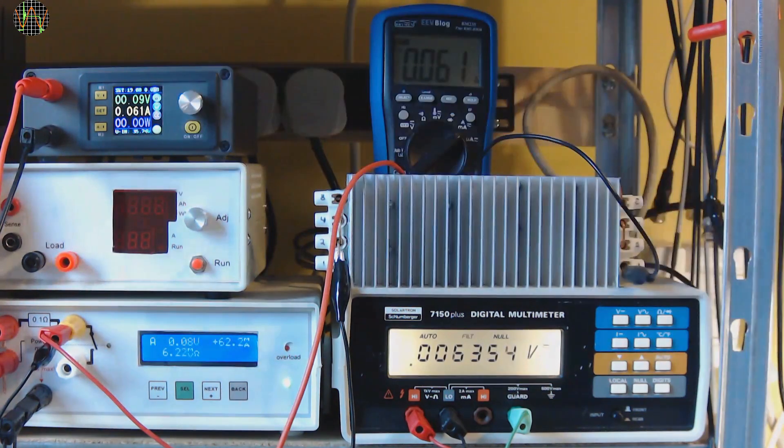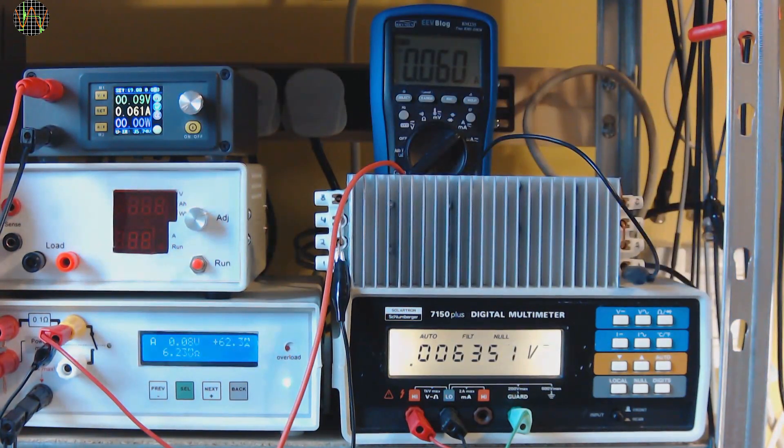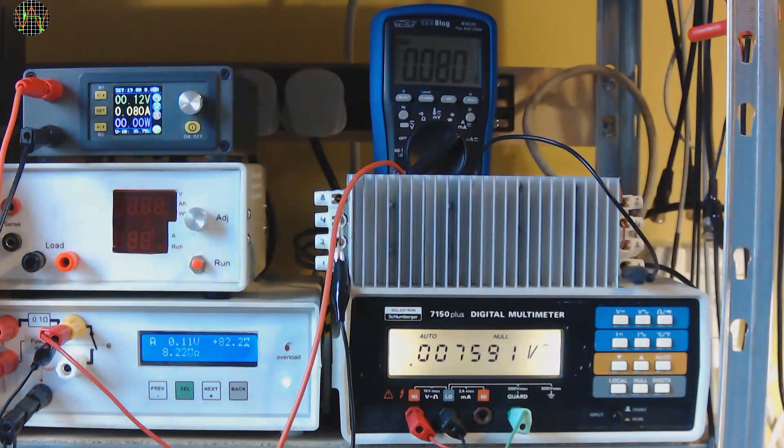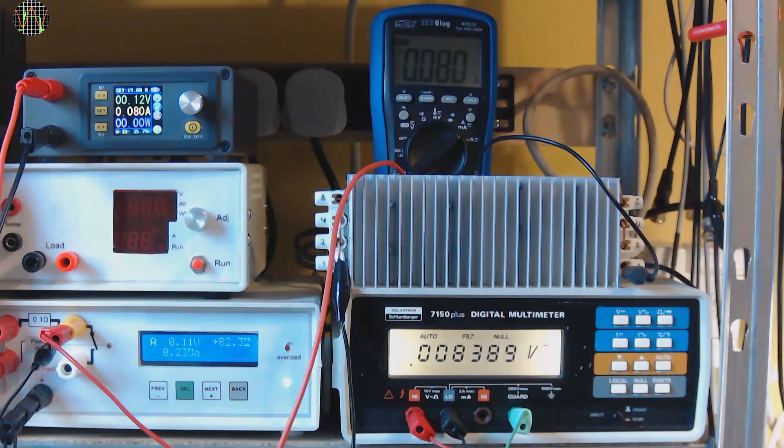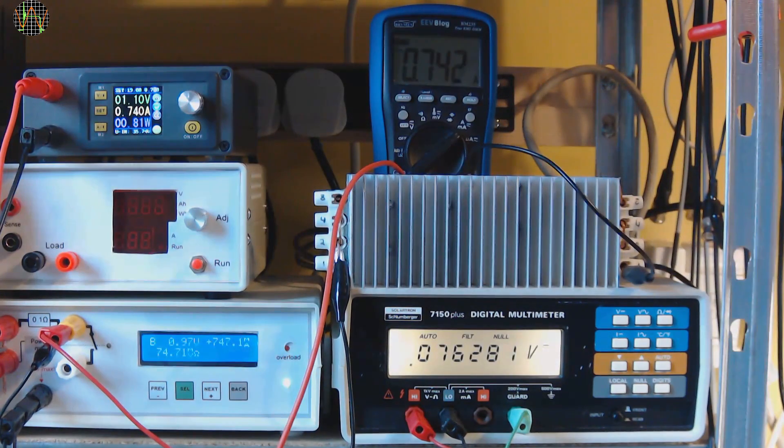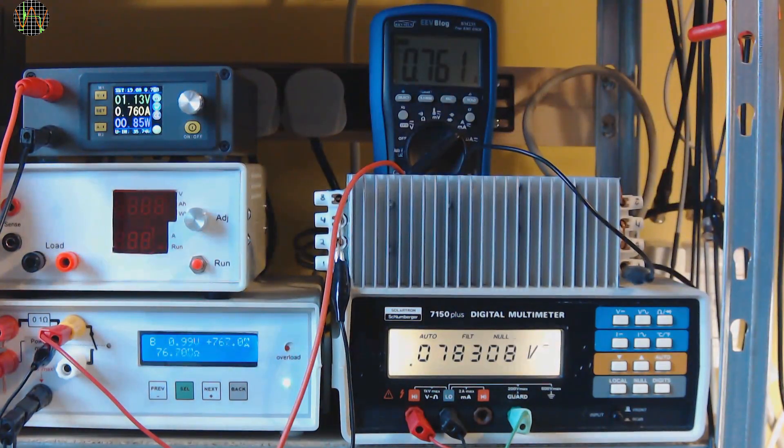For ranges A and B, I step the current limit up in 20mA steps which translates to about 2mV shunt voltage change and note the reading on the SolarTron as well as the Powermon which is shown in mV with an ohm symbol behind to indicate that it is the voltage drop across the shunt resistor.